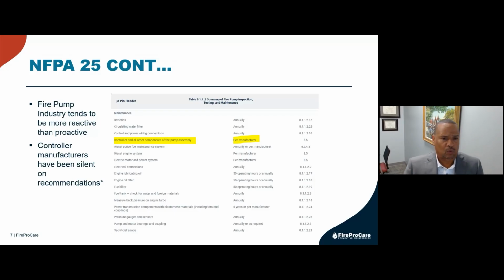Now, this Table 8.1.1.2, again, is supposed to be used in conjunction with the manufacturer's recommendations. You'll notice batteries have to be inspected, tested, and maintained annually. The water filters annually. I highlighted the controller, and what you see there is it states it's per the manufacturer, doesn't give you an interval, and then it gives you a reference to another chapter in NFPA 25, which is 8.5. Hold that thought, because we're going to take a look at that in a second and see exactly what 8.5 says. But just remember, it's per the manufacturer in accordance with 8.5 as well. So we'll dive into that.